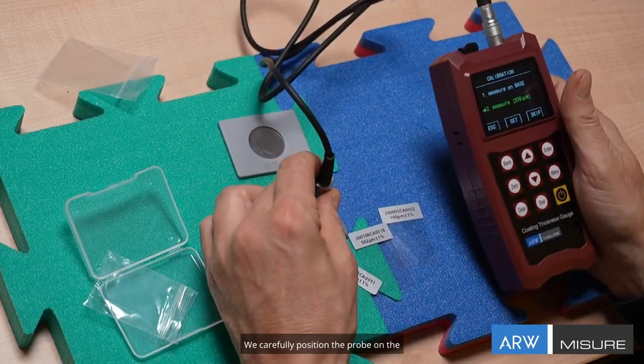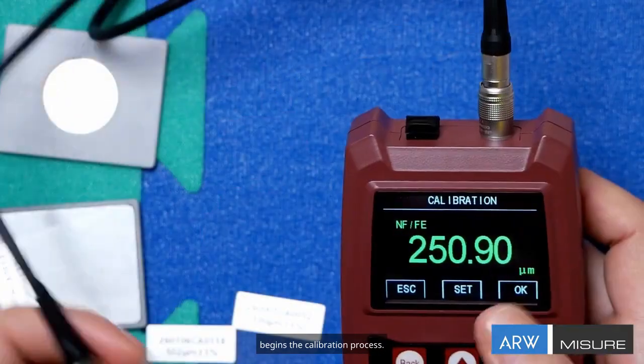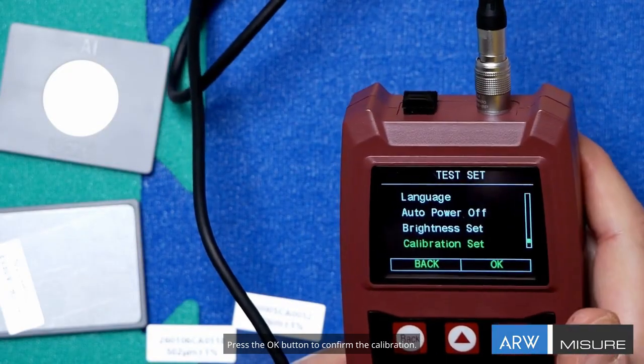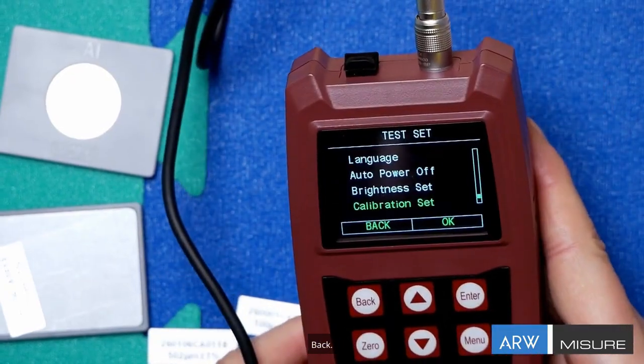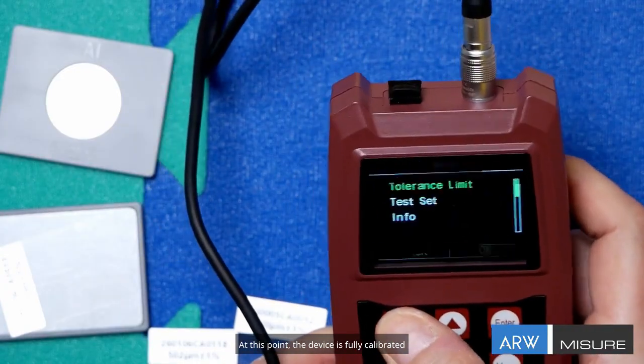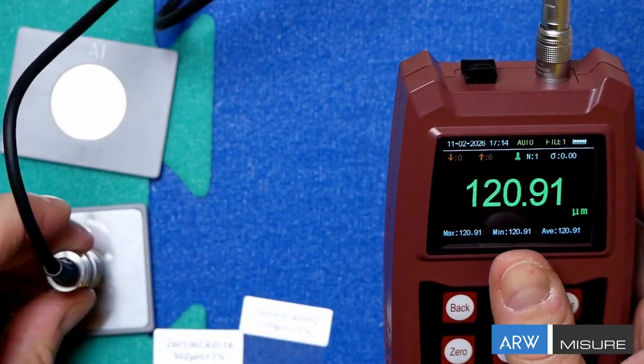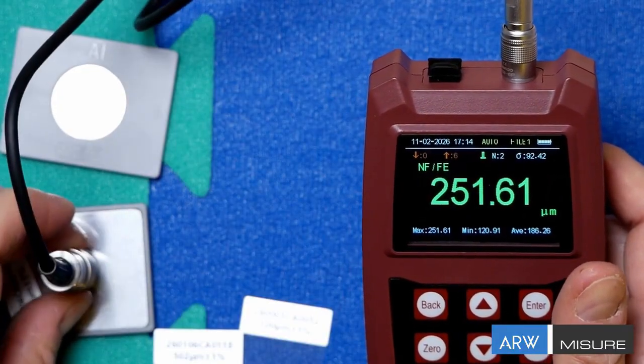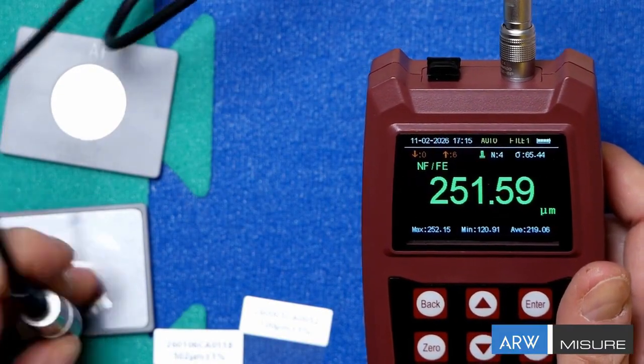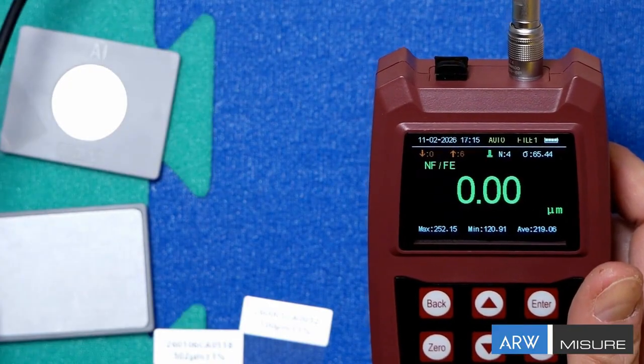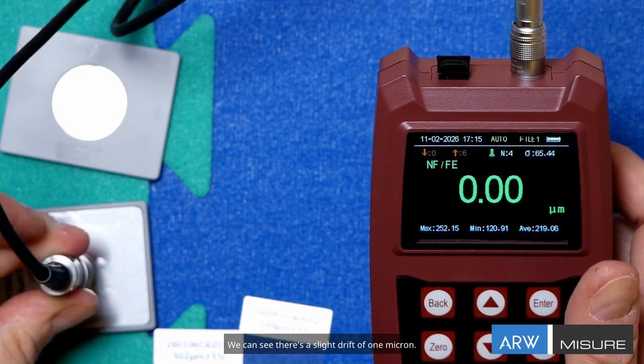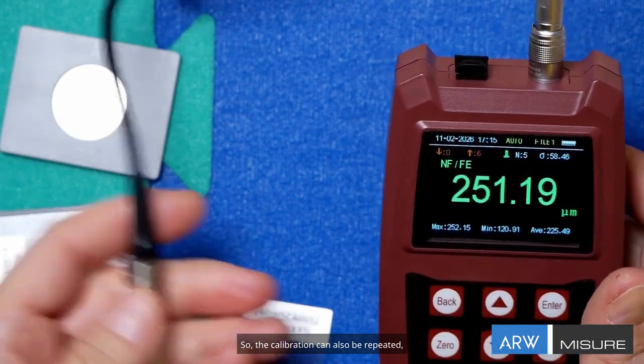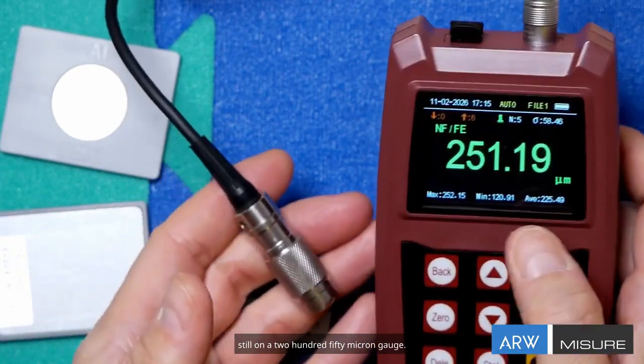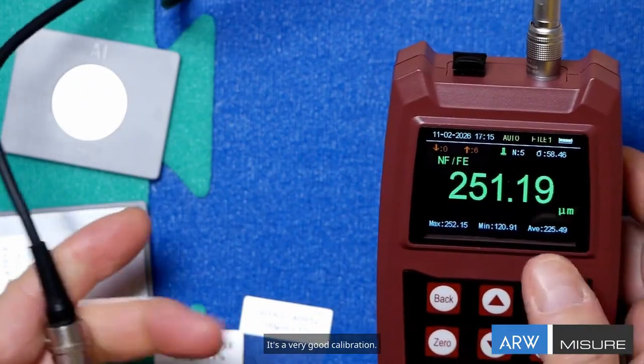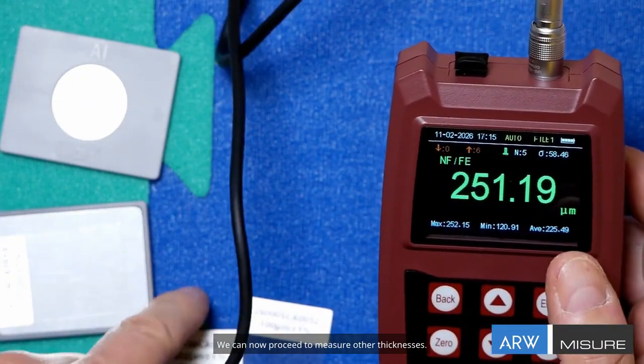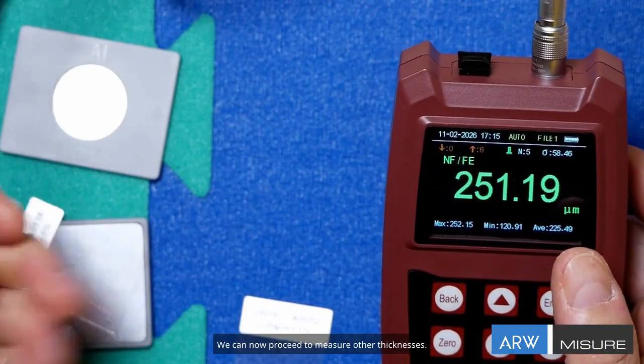We carefully position the probe on the thickness gauge and the device automatically begins the calibration process. Press the OK button to confirm the calibration. Back. At this point, the device is fully calibrated and ready for use. We can see there's a slight drift of 1 micron, so the calibration can also be repeated, still on a 250 micron gauge. It's a very good calibration. We can now proceed to measure other thicknesses.